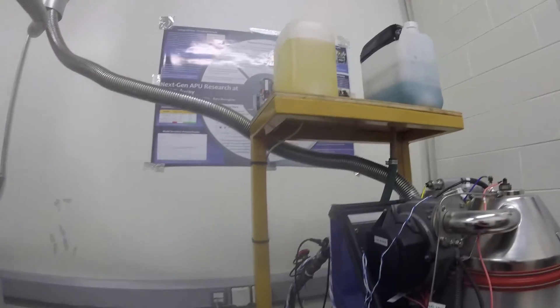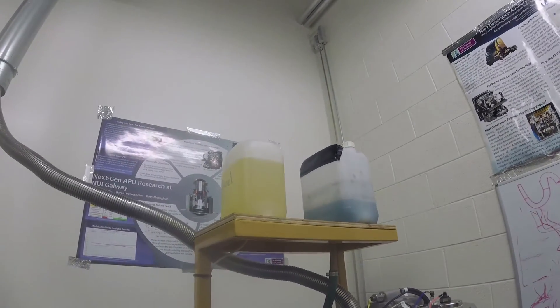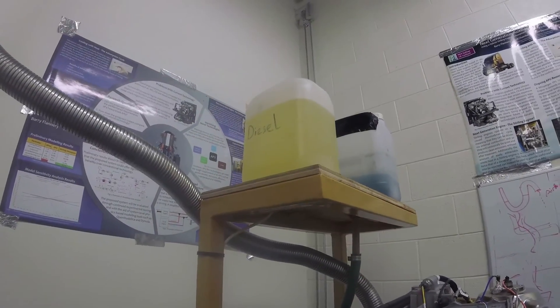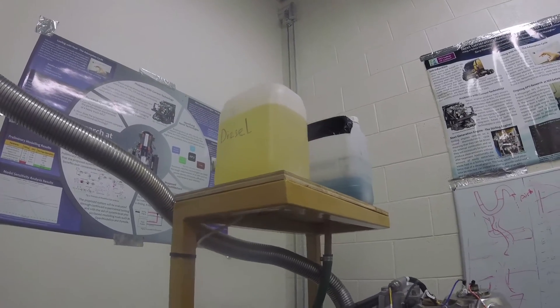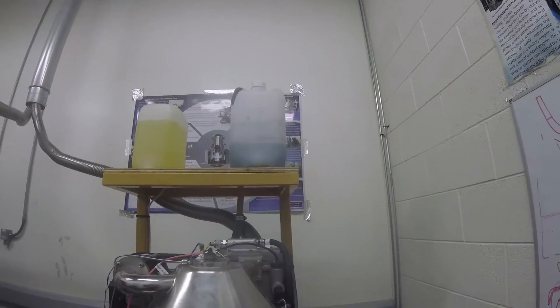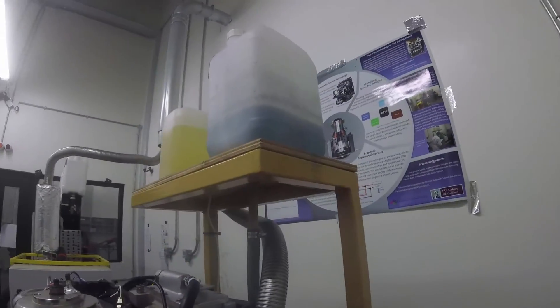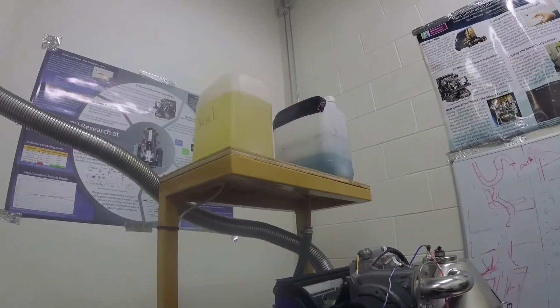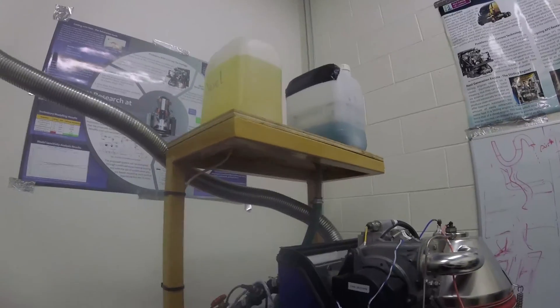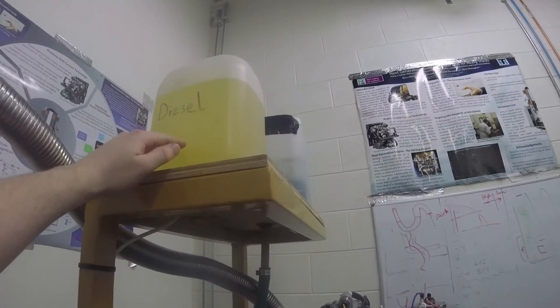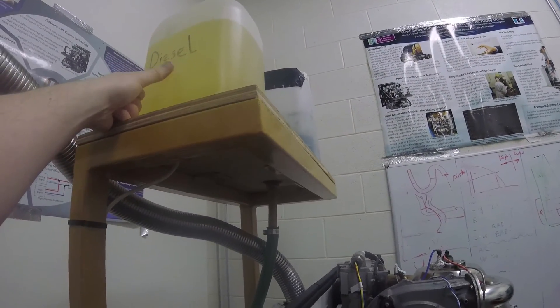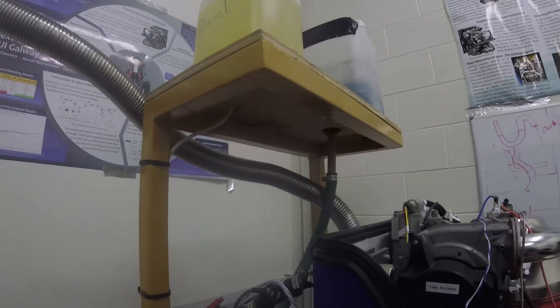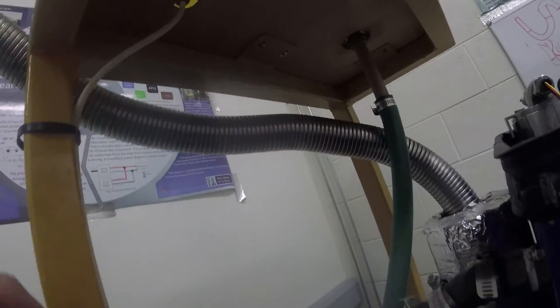Lastly is the fuel header tanks. There's diesel fuel, that's where it gets added in, up at the top up there. And likewise, there's the coolant. This is for the closed loop, it's a mixture of glycol and water. Both of these tanks are vented. That's critical. It just means that there's a little hole in the cap. That's just so that when the fuel is actually draining out of the tank or coming into the system, it doesn't cause a vacuum and cause the engine to stall. When the system is being refueled, it's important to do a quick check, make sure none of the lines are damaged here. This is the fuel line, the white line down here. Make sure there's no leaks.